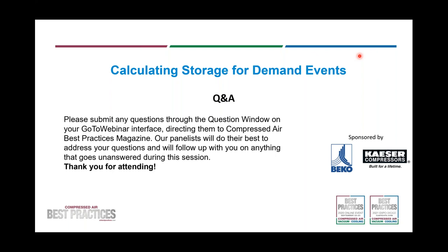Next question, for Jason from BEKO: is there a difference between dew point and pressure dew point? Pressure dew point is the dew point at whatever pressure you're operating. Atmospheric dew point would be measured at atmospheric pressure. It's important to note the difference and take it into consideration when specifying a required dew point within the compressed air system at operating pressure. If you have minus 40°F pressure dew point in the system and you release that air to atmosphere, the pressure dew point will reduce further as the pressure drops to atmospheric. So yes, they are different.